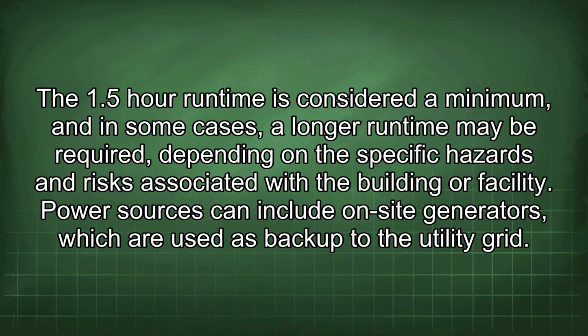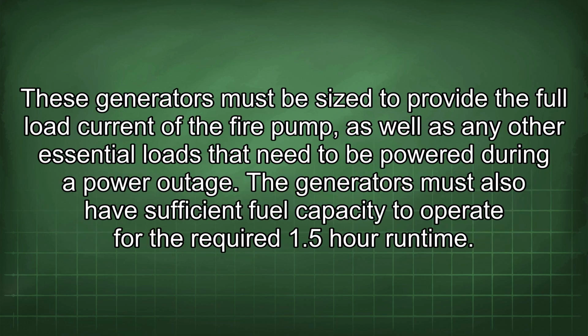Power sources can include on-site generators, which are used as backup to the utility grid. These generators must be sized to provide the full load current of the fire pump, as well as any other essential loads that need to be powered during a power outage. The generators must also have sufficient fuel capacity to operate for the required 1.5-hour runtime.